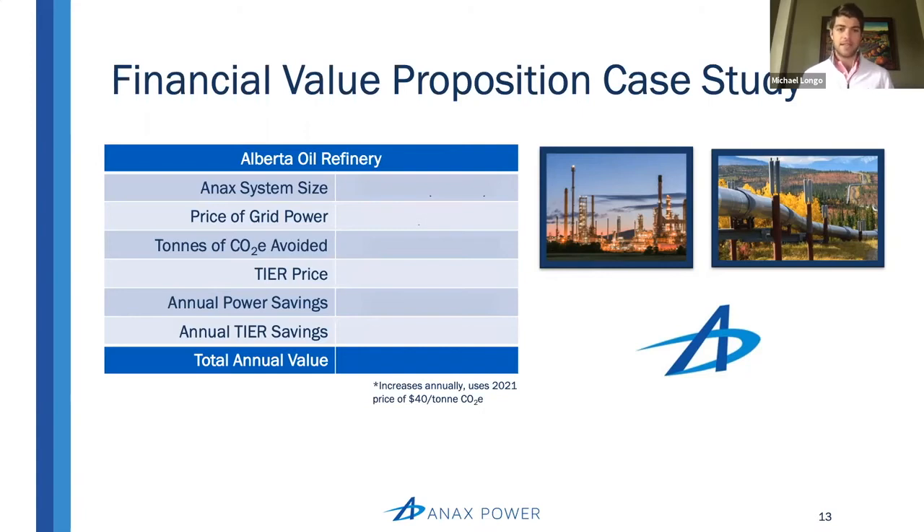From the gas conditions they sent over — again, thousands of data points — it was determined that the optimal Anax system size would be 1.5 megawatts, or three units. The price of grid power paid at this refinery is $60 per megawatt hour, a little bit high no doubt due to its remote location. The tons of CO2 emitted avoided is 0.57 tons of CO2 per megawatt hour. This is important particularly in Alberta, where for every ton of CO2 avoided per megawatt hour, they are paid $40.